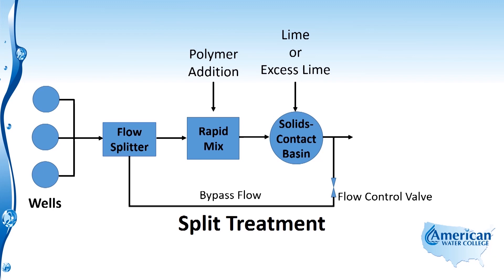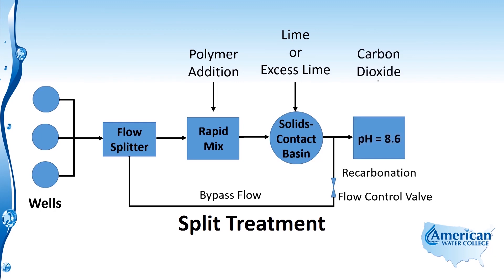Both flow streams then meet up and go into the recarbonation process where carbon dioxide is added and the pH is adjusted to 8.6. From there the water flows through filters, then to disinfection, and into the distribution system. The split treatment method is primarily a way to reduce chemical costs by treating only a portion of the total flow.